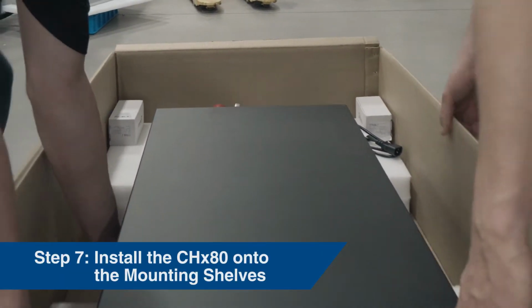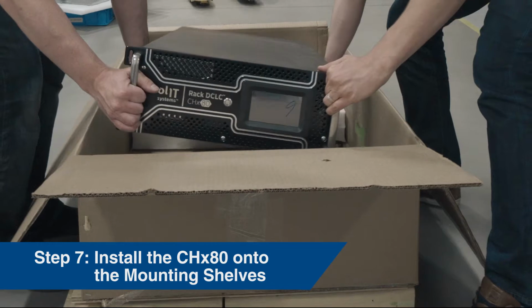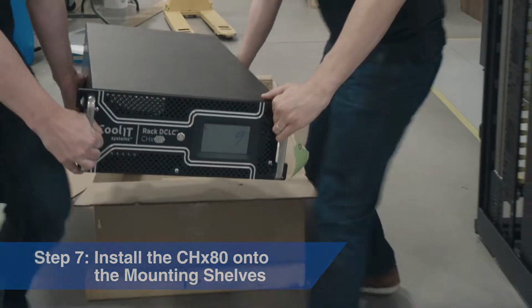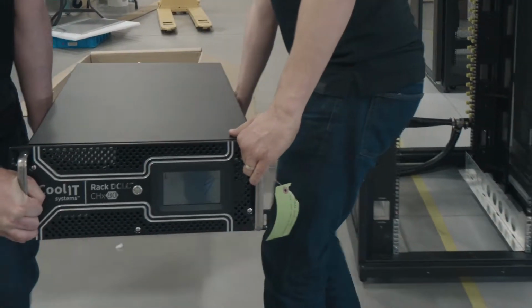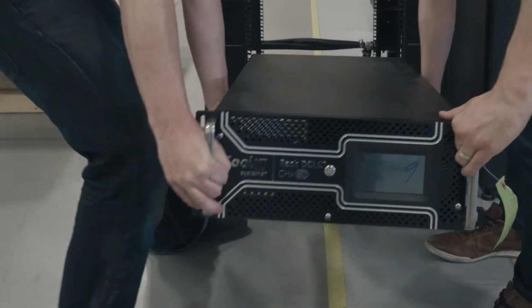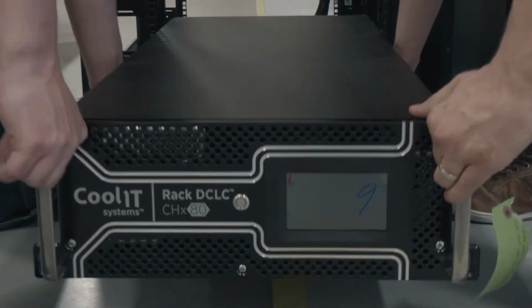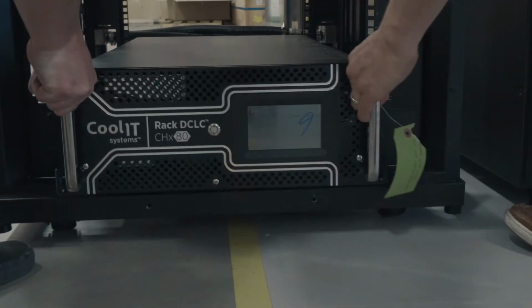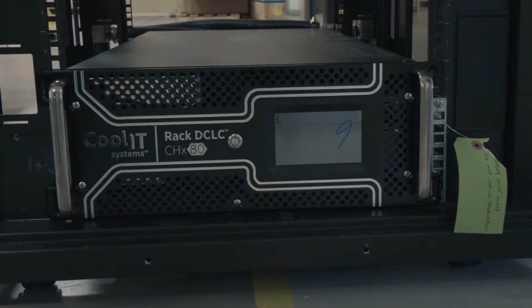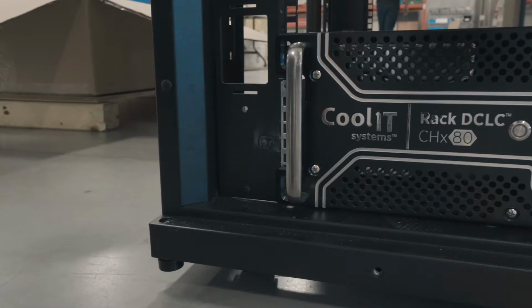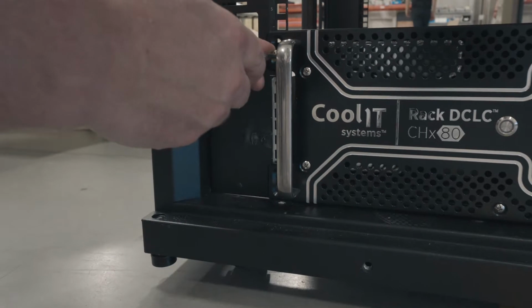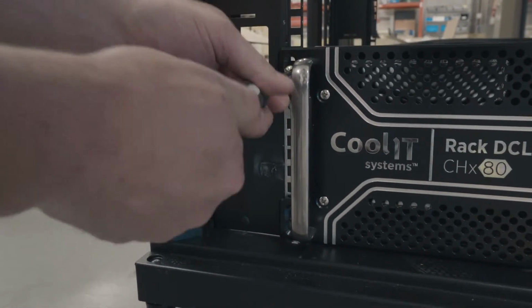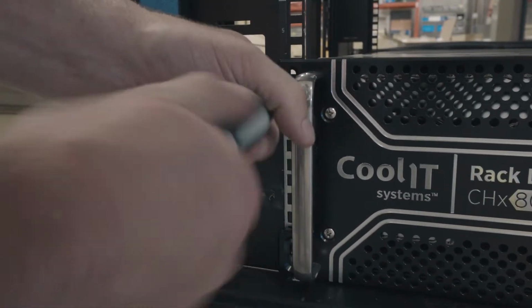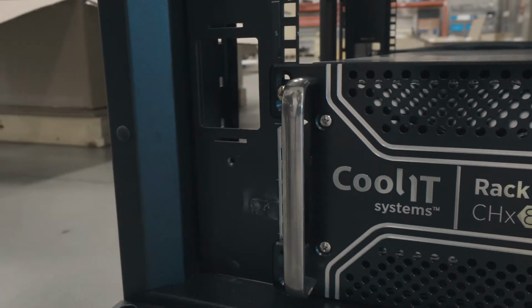Step 7. Install the CHX80 onto the mounting shelves. With 2 people, carefully remove the heat exchanger from the crate and slide onto the heat exchanger shelves in the rack. The unit can be carried by grabbing the underside of the unit and grabbing the handles on the front of the faceplate. Once in place on the shelves, secure the heat exchanger faceplate to the rack using the provided hardware.